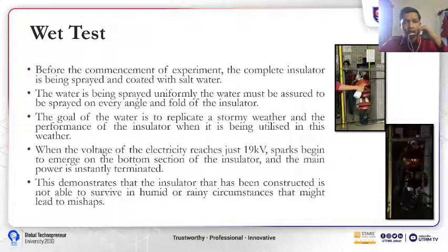And for the wet test, before the commencement of our experiment, the complete insulator was sprayed and coated with salt water. The water is sprayed uniformly. The water must be assured to be sprayed on every angle and fold of the insulator. The goal of the water is to replicate stormy weather and the performance of the insulator when it is being utilized in this weather.